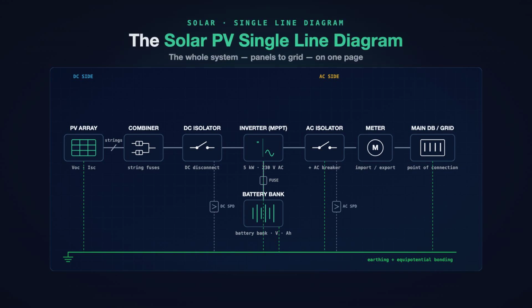This is a solar PV single-line diagram. The whole solar system drawn as one clean line from the panels on the roof all the way to the grid. If you have ever applied for a permit or booked an inspection for a solar install, this is the drawing they ask for. One page, every major part, every protection device, the way the power actually flows.